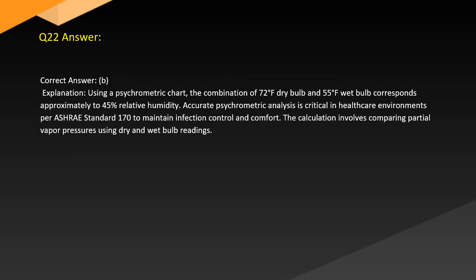Answer. Correct answer, B. Explanation. Using a psychrometric chart, the combination of 72 degrees dry bulb and 55 degrees wet bulb corresponds approximately to 45% relative humidity. Accurate psychrometric analysis is critical in healthcare environments per ASHRAE Standard 170 to maintain infection control and comfort. The calculation involves comparing partial vapor pressures using dry and wet bulb readings.